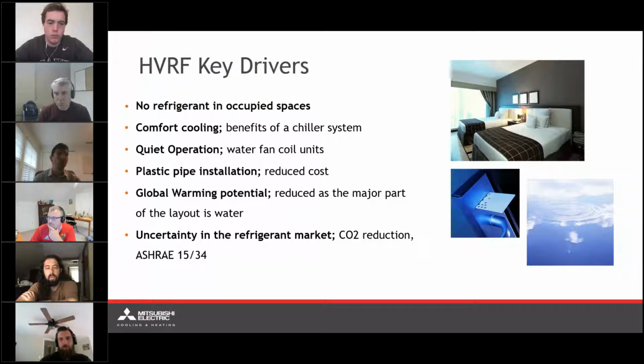But given that we're drastically reducing the amount of refrigerant in the system, we are going to be avoiding circumstances such as existing R22 systems that cost an arm and a leg to service, to top off with additional refrigerant. So even in the event that the R410A refrigerant slowly gets phased out, we're not going to need nearly as much in the system as a whole for an HVRF system.